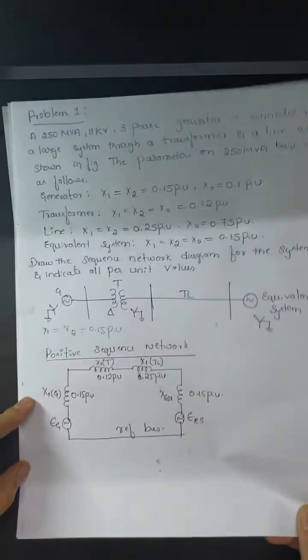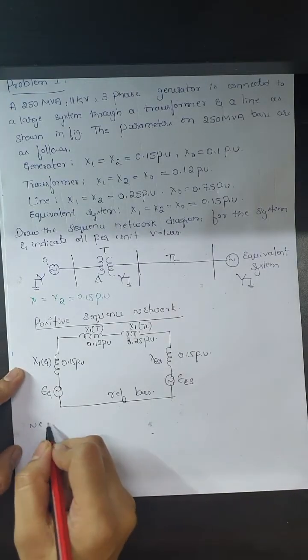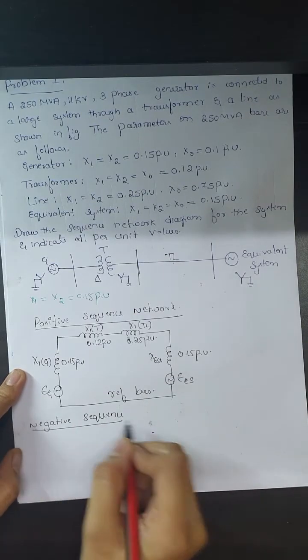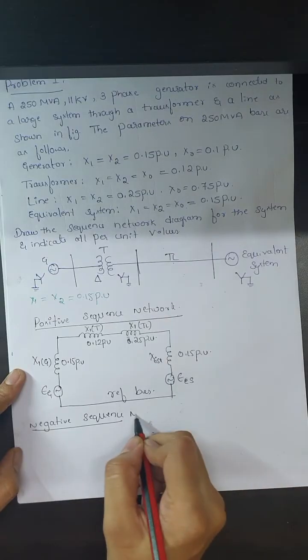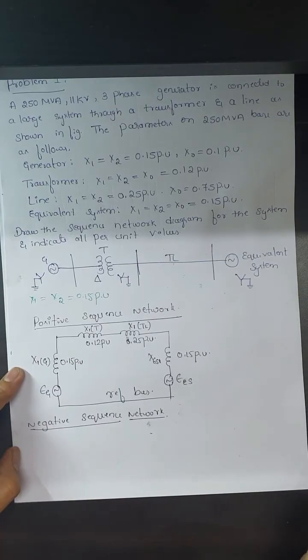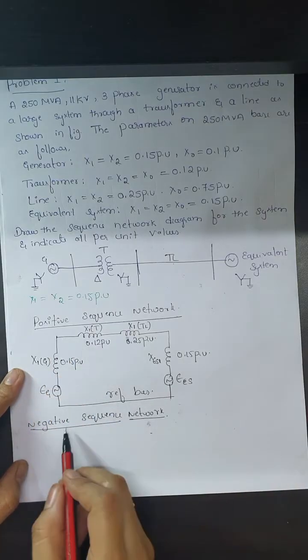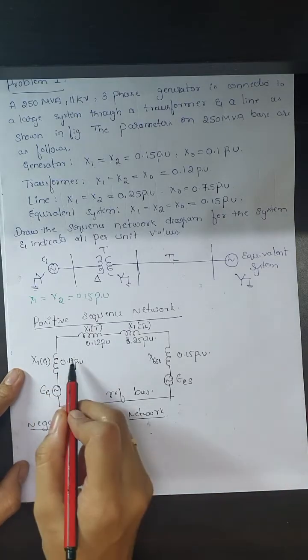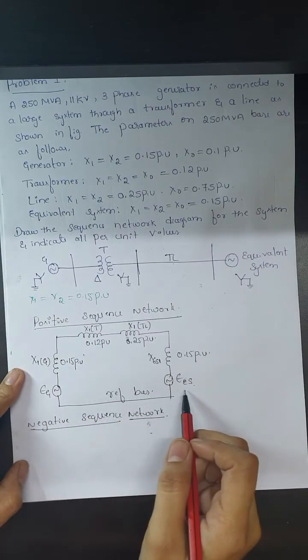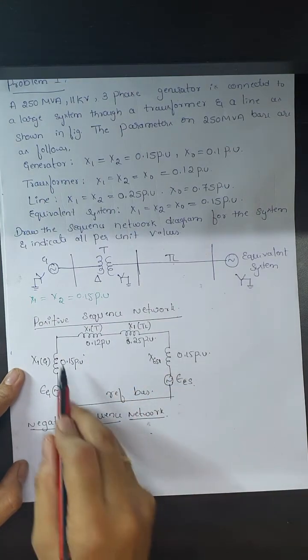Next, we draw the negative sequence network below the positive sequence network. The negative sequence network is just similar to the positive sequence network, but the source voltages Eg and Es will not be present in the negative sequence network. Excluding these two source voltages, the remaining parameters are retained in the diagram.